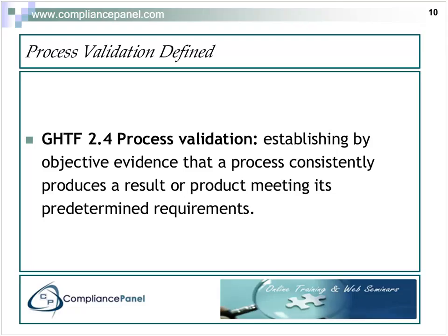So we're trying to repeat time and time again meeting those design requirements for this particular medical device, whether it be the final product or the components that go into the product. And I might add, we don't care who those products or components are produced by, whether it is a supplier or the manufacturer. In the end, the manufacturer is responsible for the process validation that is required for that particular product.